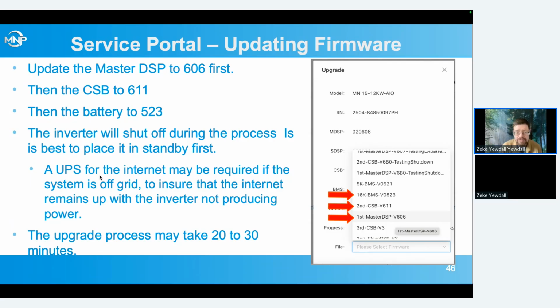Because the inverter shuts off during the upgrade process, it's always best to just put it in standby first. It's not good to have it suddenly shut off while you're doing the upgrade. And every once in a while, it can actually cause some really bad things to happen. So it's best to always put it in standby first.